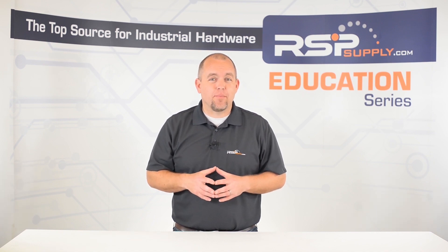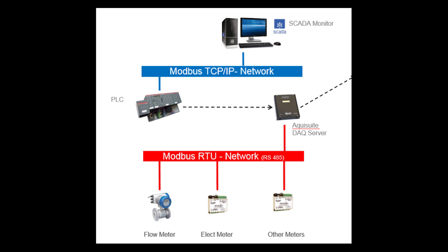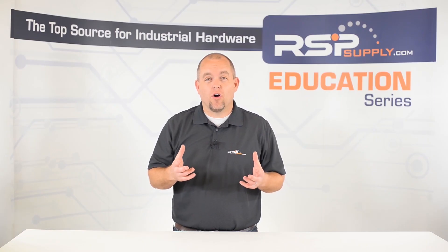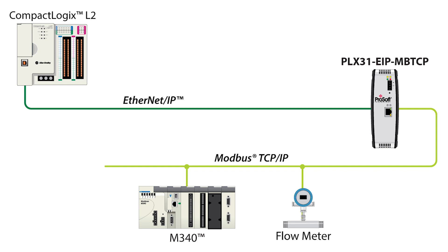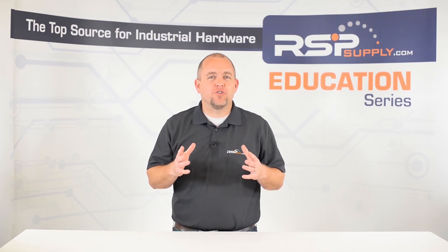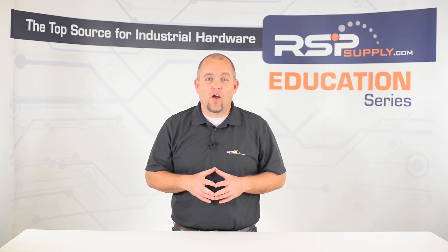When designing a new system, this can be very helpful. Let's assume that a client is wanting to use a Modicon PLC for a new plant environment. Modicon PLCs use the Modbus protocol. So when trying to integrate other types of hardware into this system, it would be advantageous to select hardware that uses the Modbus protocol. If a situation is encountered where various pieces of hardware use different communication protocols, they will not be able to communicate with each other. In this scenario, it would be necessary to use another piece of hardware that can interpret one communication protocol and convert it to another type of protocol. These converters are very common and are used all the time to deal with these types of issues.